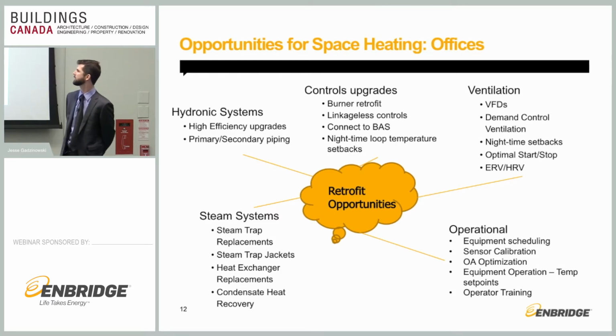Steam trap jackets, it's kind of a newer thing that we've been promoting. It's just essentially putting a 1-inch piece of insulation layer around your steam trap, because the steam trap is essentially an exposed piece of pipe with 200 degree Fahrenheit steam in there, so it's just radiating heat. So it's the steam trap jacket you can put over it and just contain that heat loss.